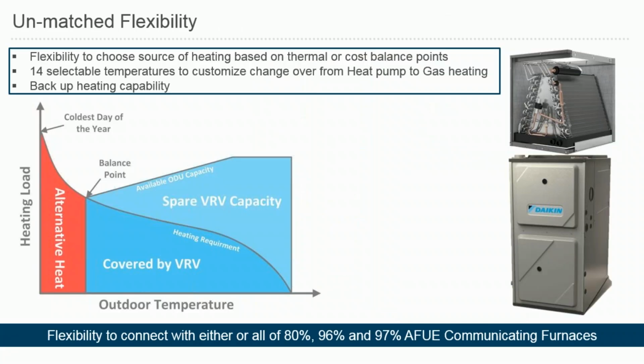So how you're going to do this will be included in the installation manual. Basically, you will be picking a changeover temperature or a balance point to switch from heat pump heat to gas heat, or vice versa. And I think the default outside temperature will be 35 degrees for this to happen, but in the installation manual, you'll see that you have a lot of different options that you can pick.